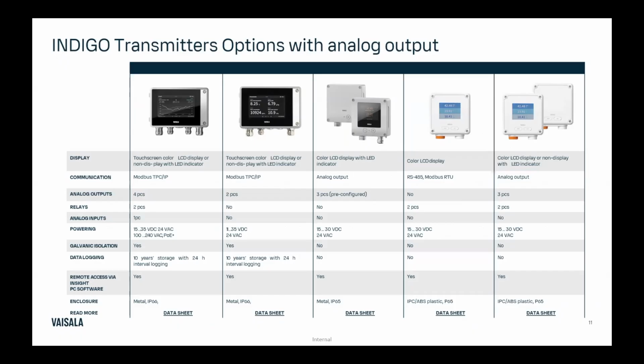I also will highlight our portables later on, but I'll move from right to left here. These white boxes here are our Indigo 200 series. That consists of our Indigo 201 and Indigo 202 transmitters. The Indigo 201 offers 3 analog outputs, a display and non-display version, and is also configurable through USB. And then the Indigo 202 is really more of just a display because its outputs are Modbus RTU over RS-485. So it's the same as the probe, but it would be if you wanted to have a wall-mounted display, so you could see those readings in real time rather than seeing them back at your controller.